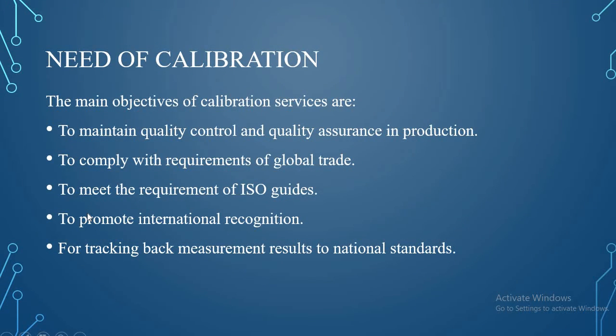So why do the measuring instruments require calibration? So here the need of calibration is given. The main objectives of calibration services are to maintain quality control and quality assurance in production. Then next is to comply with requirements of global trade and to meet the requirement of ISO guidelines. Also to promote international recognition. And the last one is for tracking back measurement results to national standards. That is, the measurements which were taken in the past can be compared with the national standards.